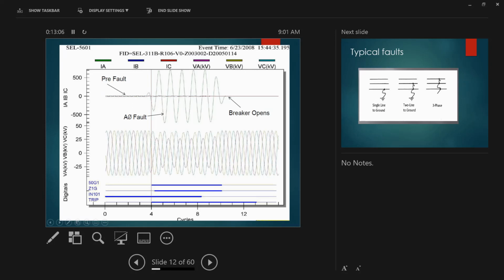The balanced current will not balance anymore once you incept the fault. The fault current will spike up, and of course the voltage on that specific phase will be affected as well. So on the relay protection, that's what you want to know: what is my available fault on that specific part of the breaker? That's why you see different kA, different settings, and also the disturbance of the voltage will be picked up by the relay.